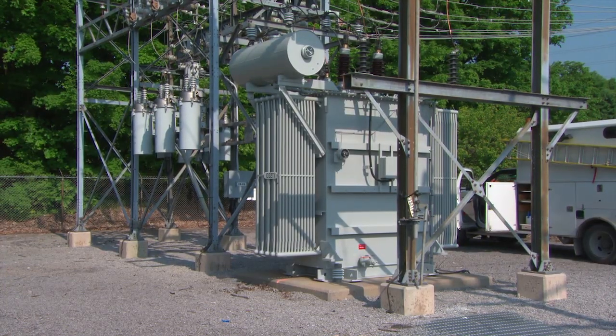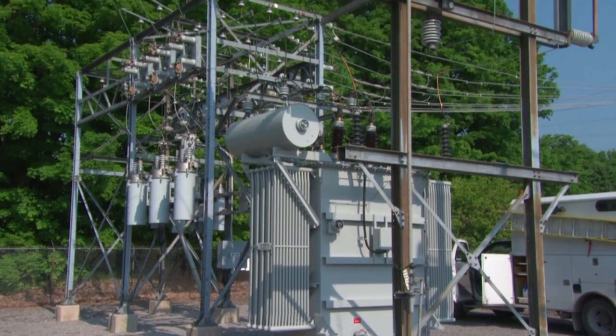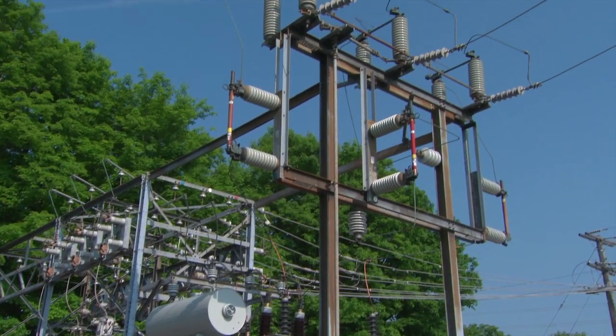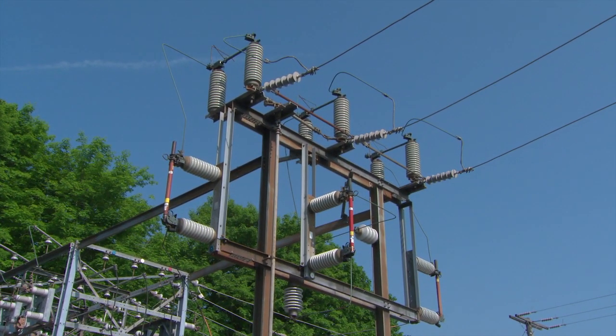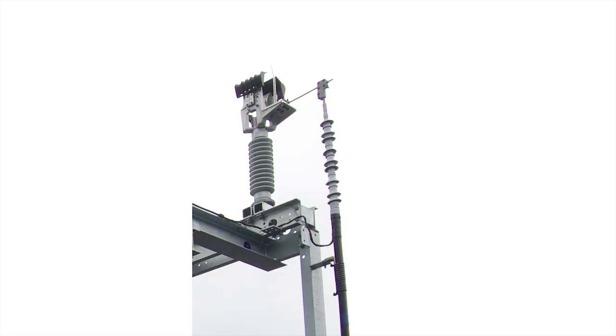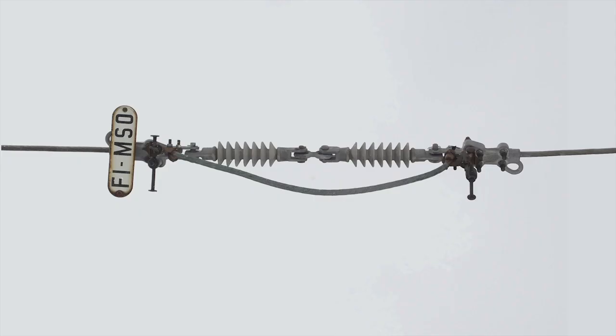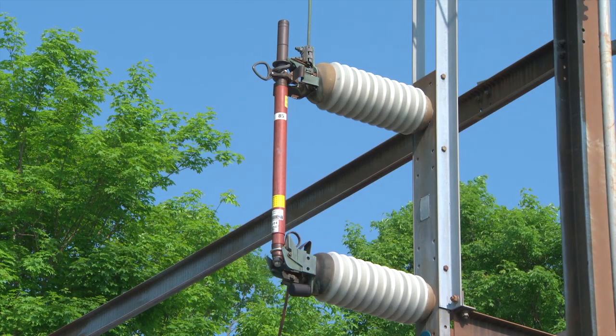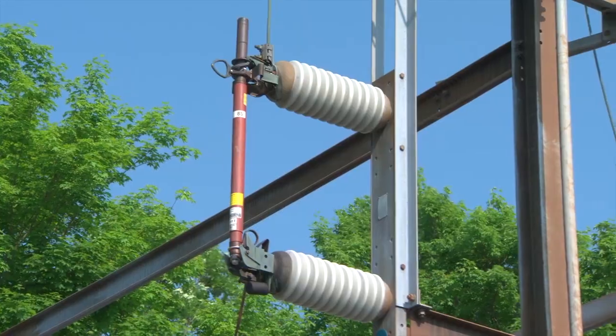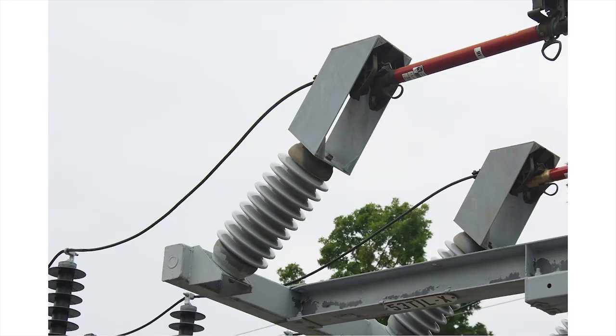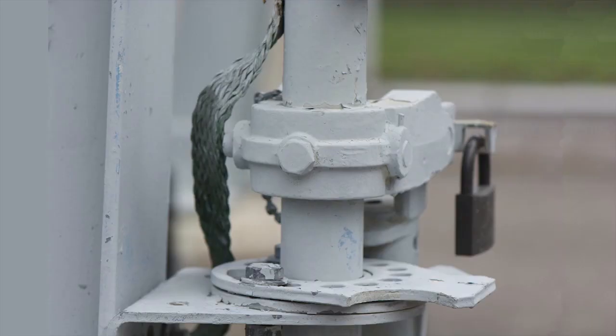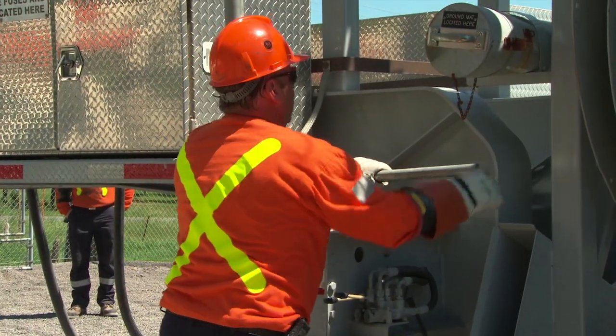Inspect the station for any obvious signs of defect, such as cracks, chips, or tracking on insulators, bushings, and surge arresters. Damage on potheads and cable terminations. Signs of arcing. Failure of the MSO assemblies. Fuses not seated or latched correctly. Insulator cap separation on the fuse jaw of the S&C fuse combo switch, or the grub screw improperly secured on the 44 kV switch drive pipe on the T-L.